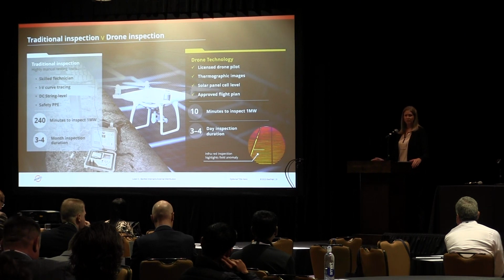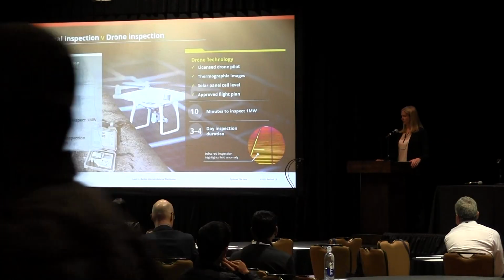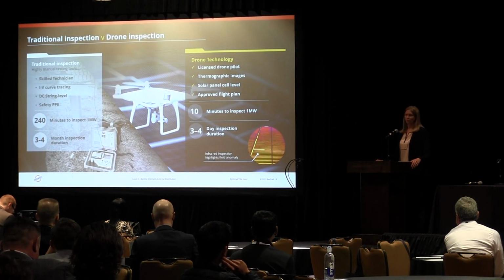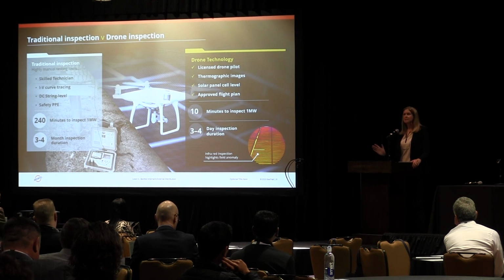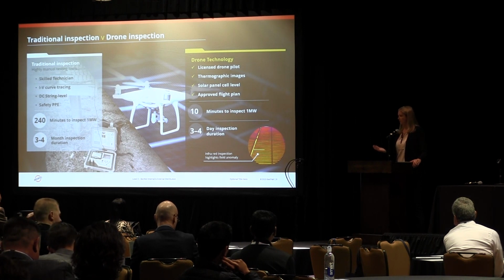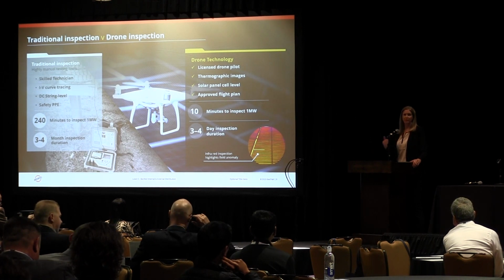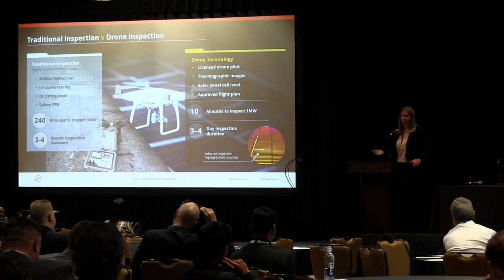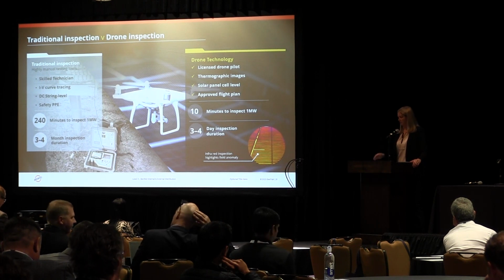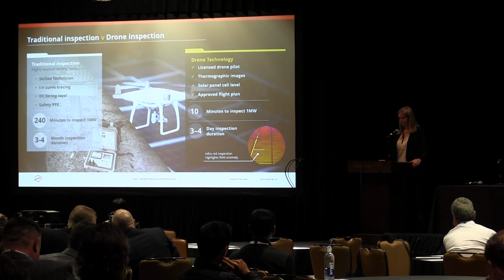IV curve tracing used to take us 3.5 to 5 hours per megawatt, which would be like 3 to 4 months to do the whole field. With thermal imaging, we can do that in 3 to 4 days. We gather all the imagery, and processing usually only takes 2 to 3 weeks. So we can find issues very early in the process and support our customers through commissioning.